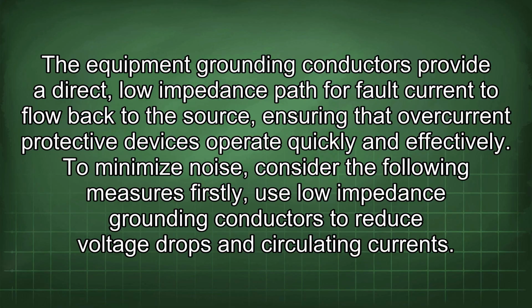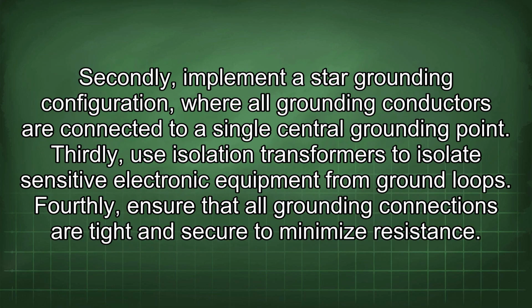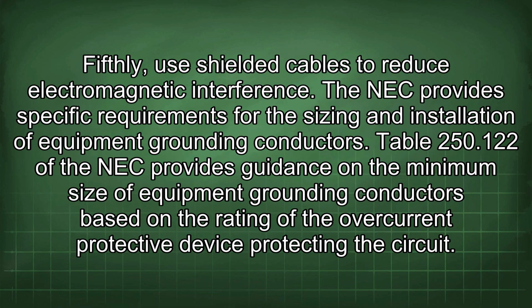Firstly, use low-impedance grounding conductors to reduce voltage drops and circulating currents. Secondly, implement a star grounding configuration where all grounding conductors are connected to a single central grounding point. Thirdly, use isolation transformers to isolate sensitive electronic equipment from ground loops. Fourthly, ensure that all grounding connections are tight and secure to minimize resistance. Fifthly, use shielded cables to reduce electromagnetic interference.